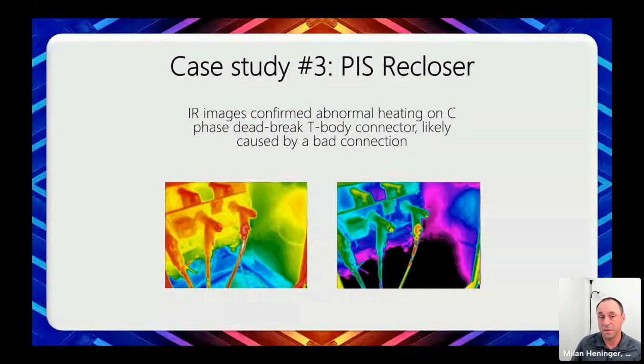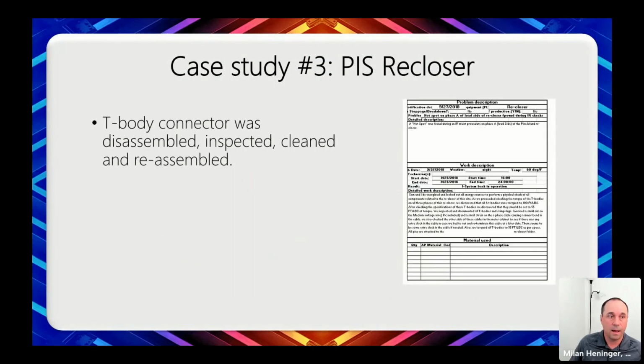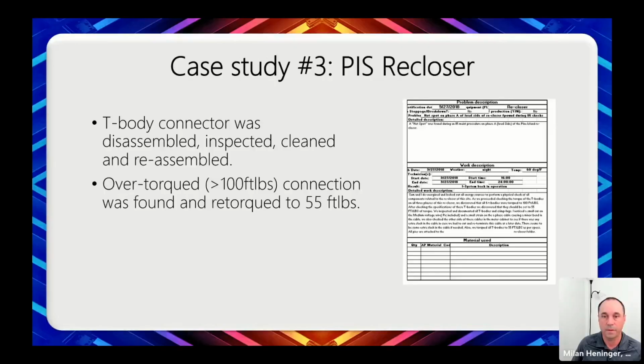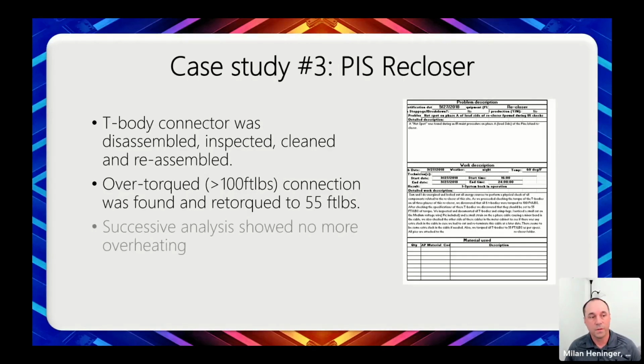Our first inclination was maybe it was loose based on what we were seeing, but that was actually not the case. Our technicians went in there, they disassembled the T-body connector, cleaned and inspected everything, and what they found was that it was actually an over-torqued connection. It was over 100 foot-pounds. Once they corrected everything back down to the 55 foot-pounds that was appropriate for that particular T-body, we found that there was no longer any ultrasound emanating from that, nor was there any overheating.